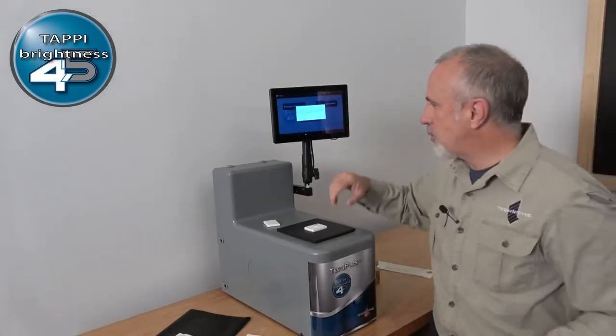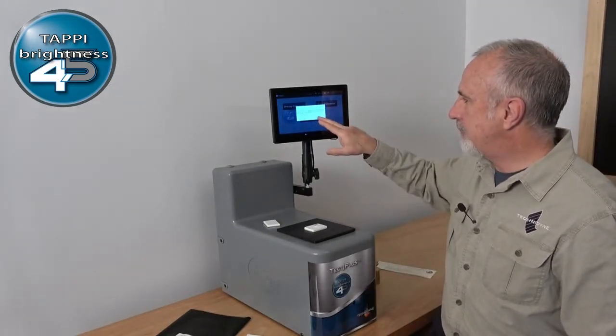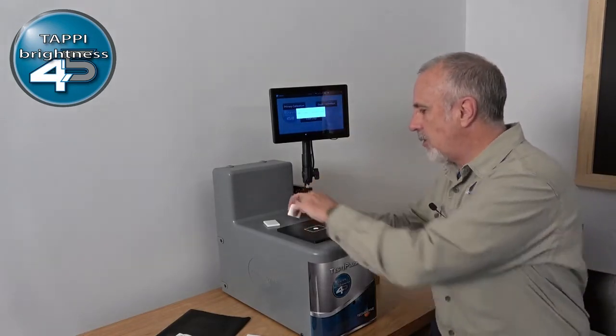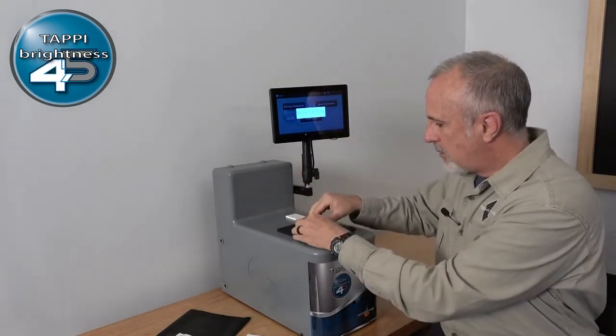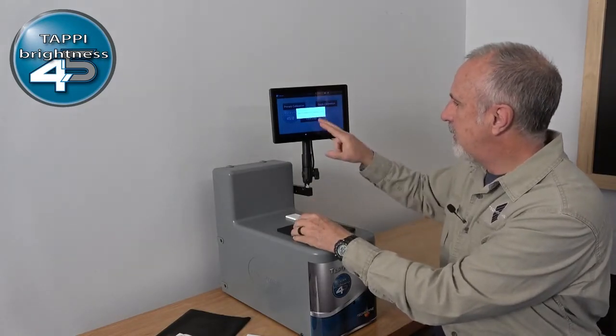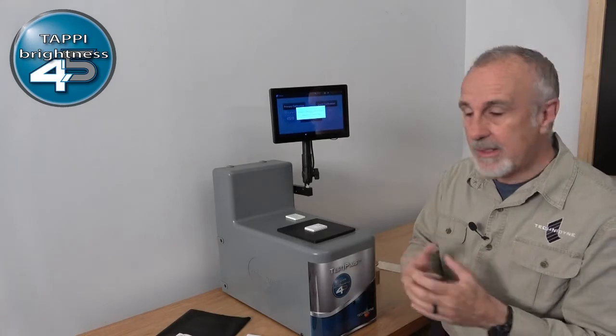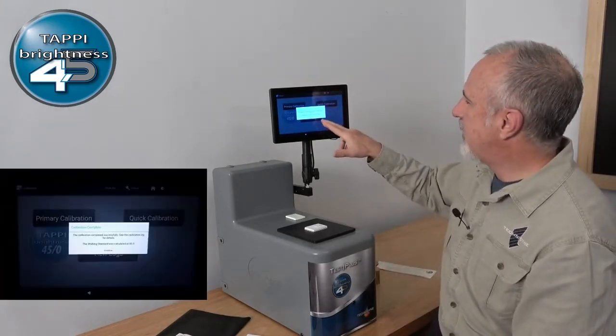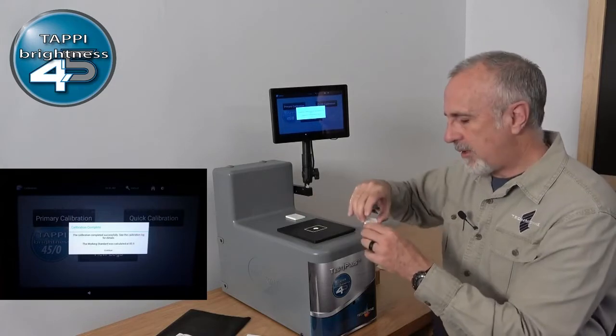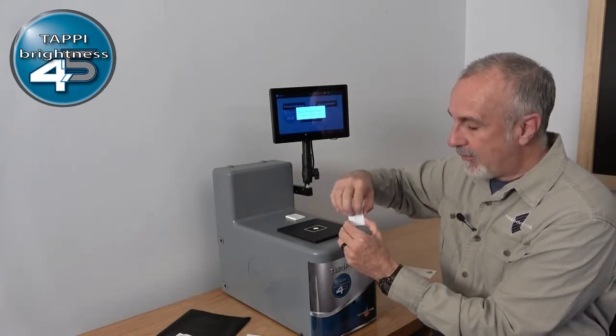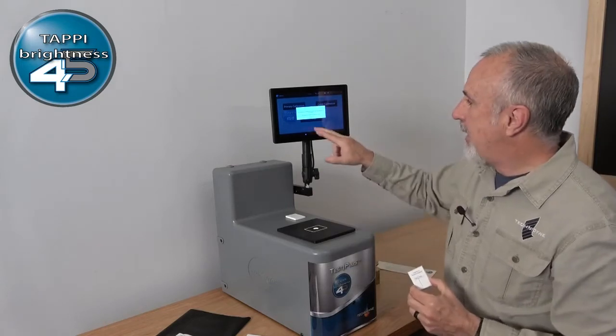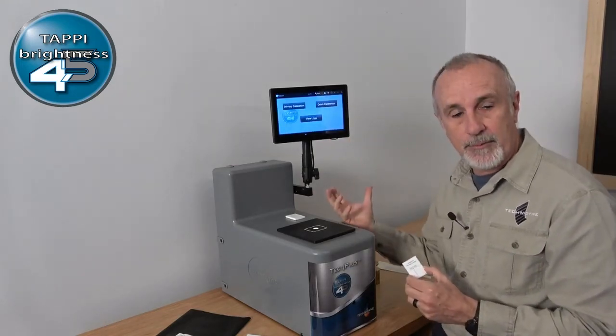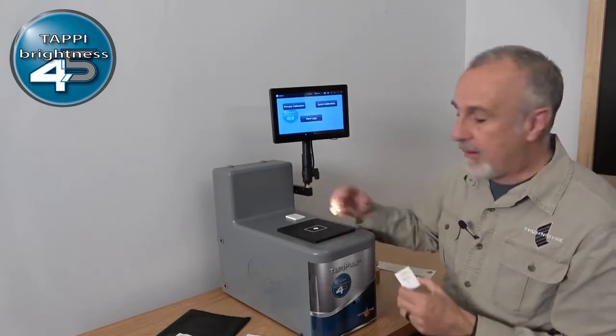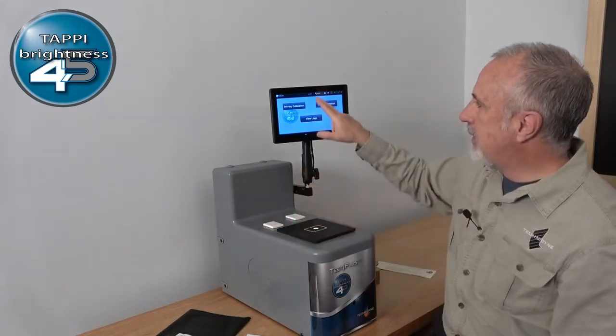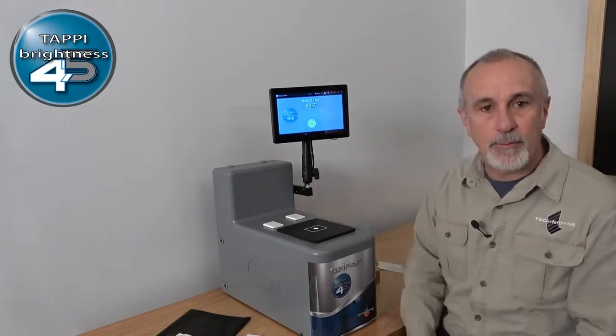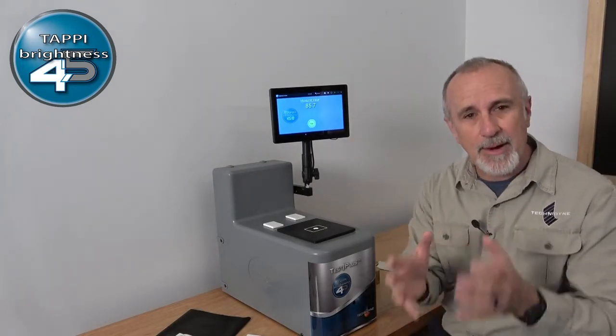All right, so once we're good with that, we hit calibrate, and it tells us to load the working standard. So I now load the working standard and hit next, and now it's going to assess the working standard value. Once I have that 85.8, what I would next do is write the date on the back of the tile, and I would write 85.8, and that would then be stored in the memory of the instrument so that when I want to do a quick cal, I can. Once the calibration is complete, I hit the home icon, and I'm back to the home screen, and I'm ready to do testing. All right, so that's the primary calibration.